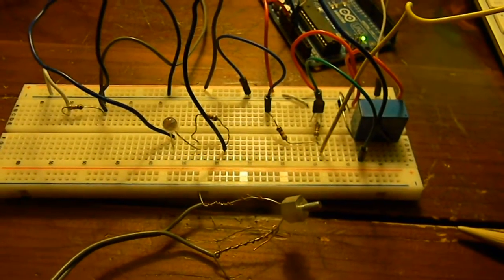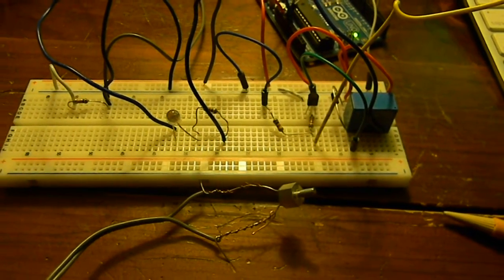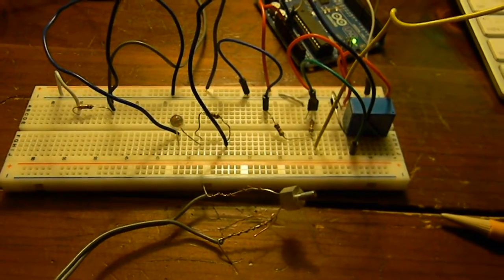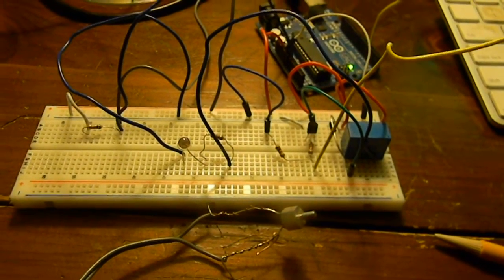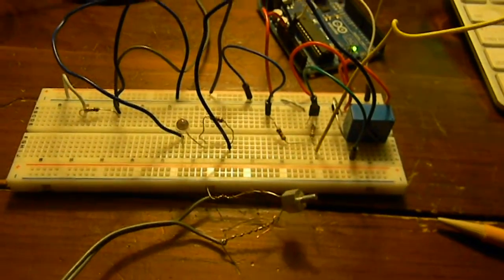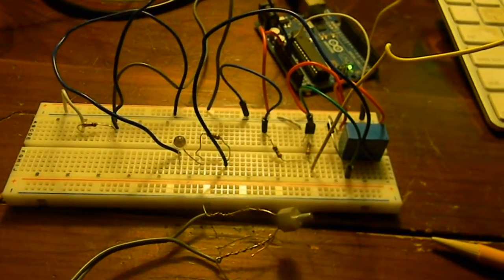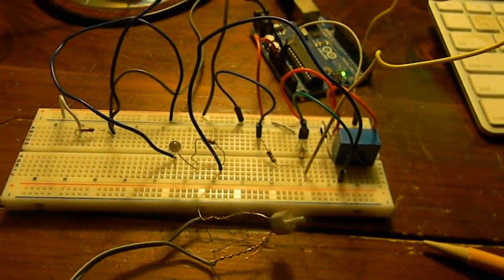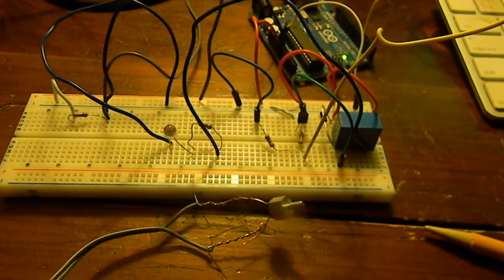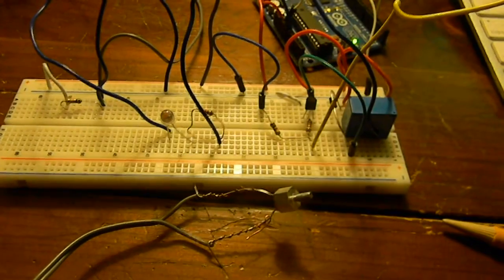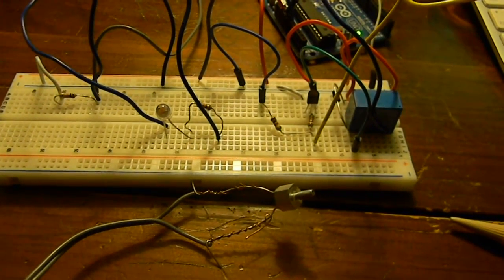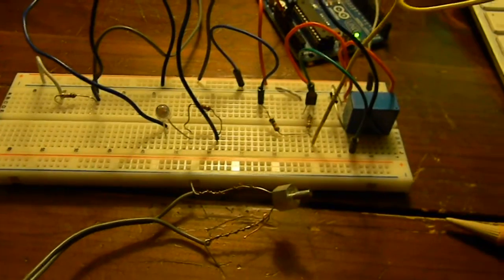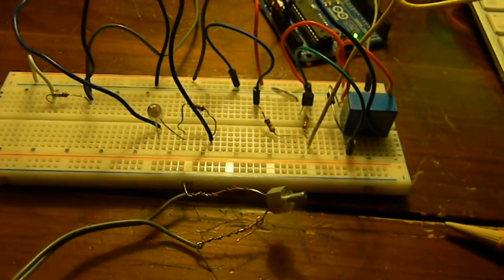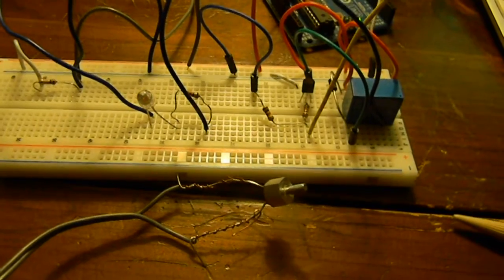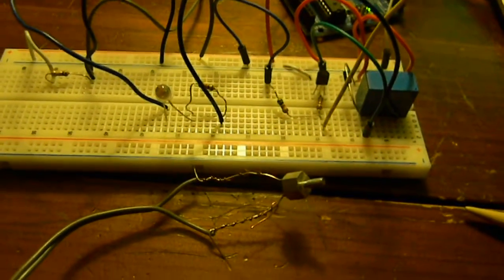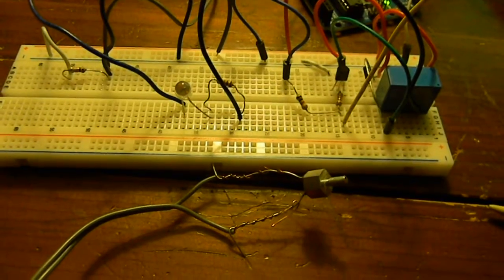Think of the LED as the 120 watt light bulb, which is heating up our reaction mixture. Once it gets to a specific cutoff temperature — in our case for a thermocycler it might be around 90 to 93 degrees centigrade — it's going to turn back off. You want to have a difference in temperature in the code so it's not bouncing back and forth on a particular cutoff; that's why you always want a hysteresis loop. So vary the code cutoff between half a degree to one degree based on your application. Right now we're at 24.73 degrees centigrade.